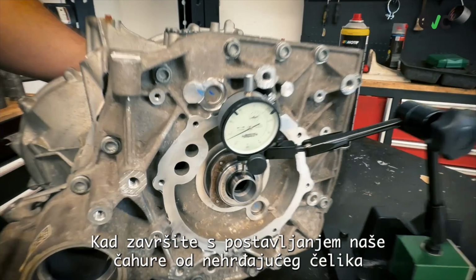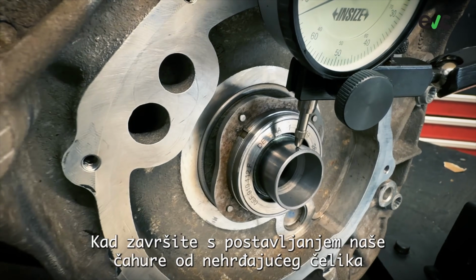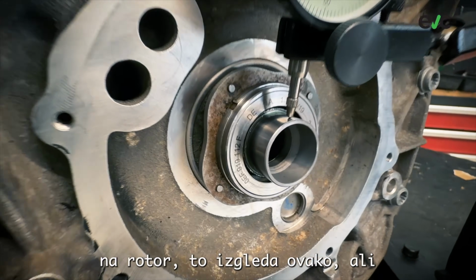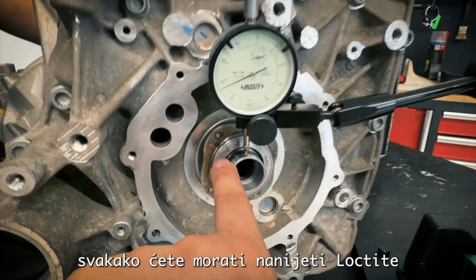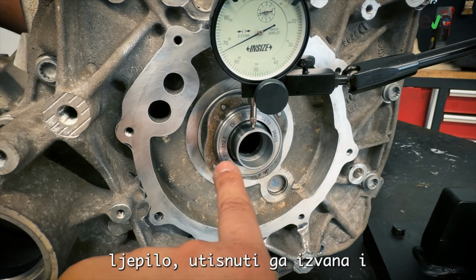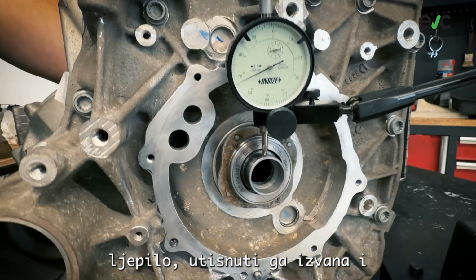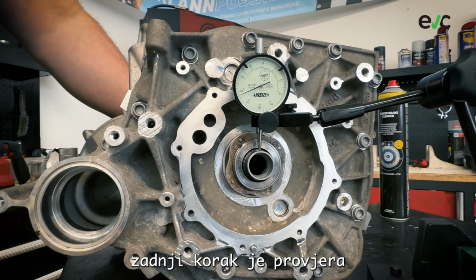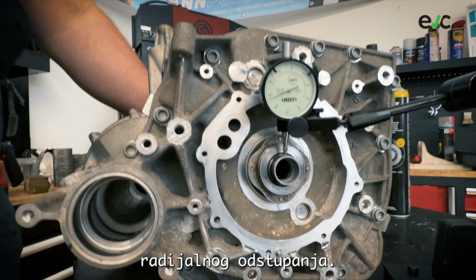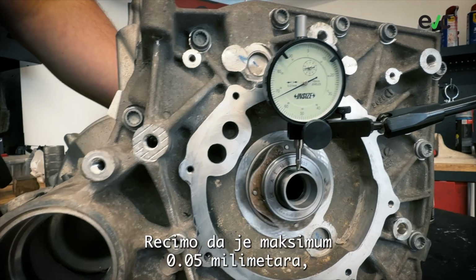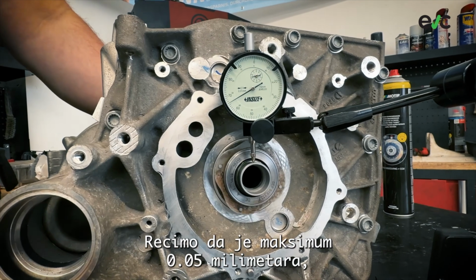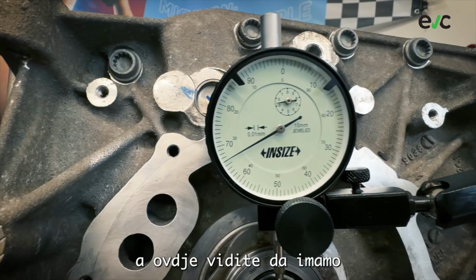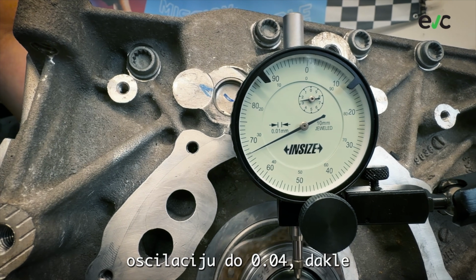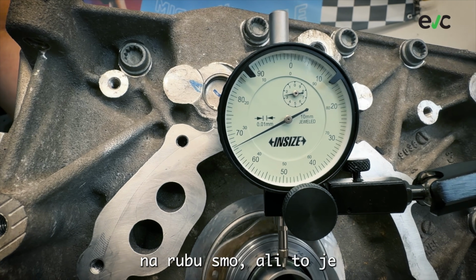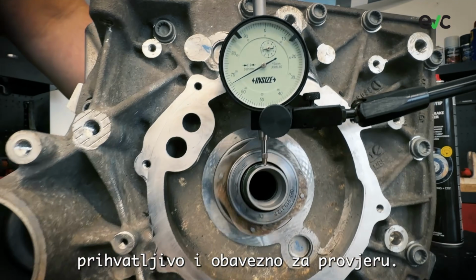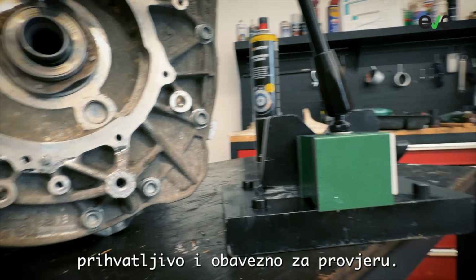When you finish installing our stainless steel sleeve on the rotor, it looks like this. You will need to put the Loctite glue, then press it in from outside, and the last step is to check the circular rotation gap. Maximum is 0.05 millimeters, and here you can see we have oscillation up to 0.04, so we are on the edge, but this is acceptable, and it's mandatory to check.